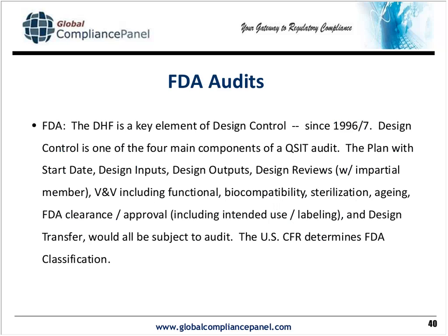Now, as I mentioned earlier, the FDA will look for design control by looking at your design history file. Under QSIT, they will take your most high-risk product, the one that has the highest risk to the patient population, and the first time they audit your company, they will audit that one product. The next time, they will take the next highest risk product and audit it against the QSIT model, which I mentioned earlier and which I urge you to download if you haven't done so on the FDA's website, and so on. If you're doing internal auditing, you should audit all of your products and all of your systems each year, annually, and maybe subparts every 12th of the year, each month, if you will.